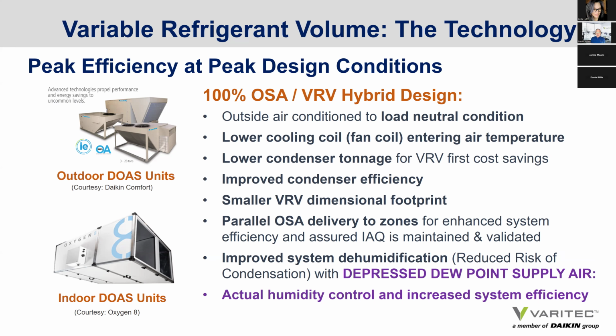Well, if you reduce the condenser tonnage, your system is more efficient at turndown and you have improved condenser efficiency. Smaller variable refrigerant mechanical dimensional footprint for your architects to take advantage of. And these systems run their outside air parallel to the variable refrigerant system, assuring and validating the outside air is being distributed throughout the building as is necessary depending on zone usage. And if you properly dehumidify the outside air at the DOAS unit, you can provide depressed dew point supply air that adds another layer of efficiency that our research demonstrates that we'll speak to here shortly.